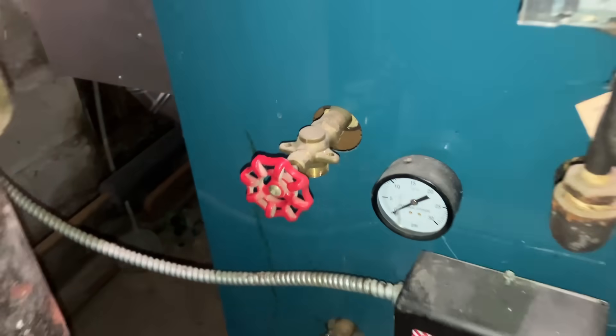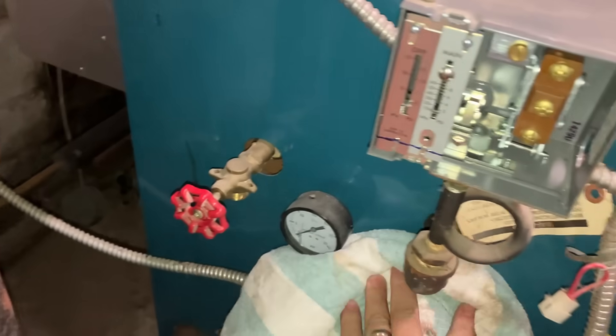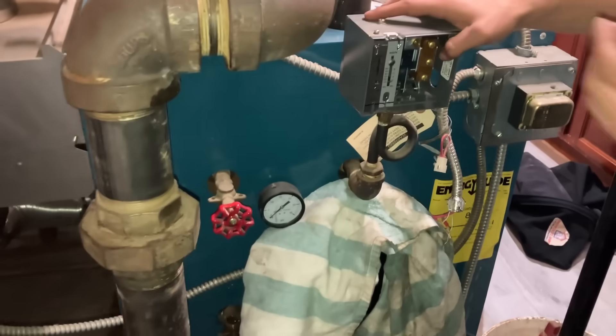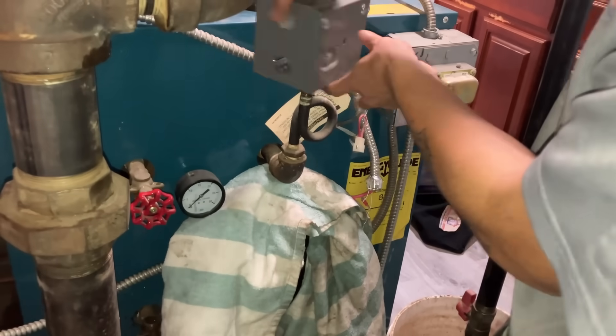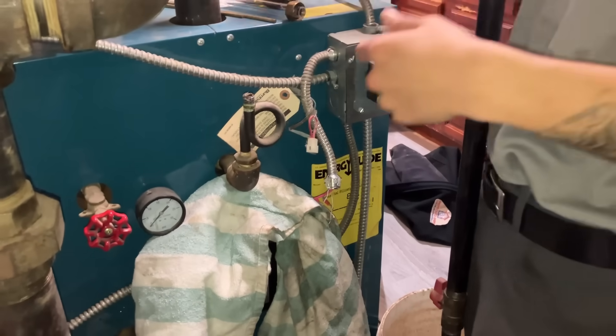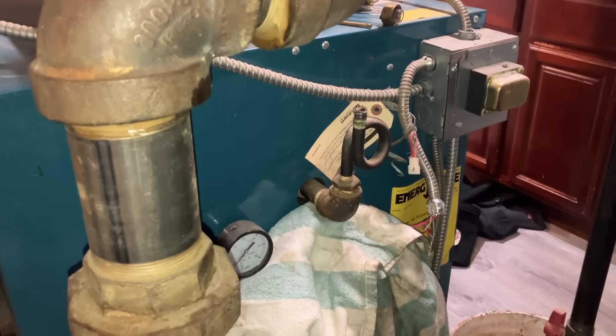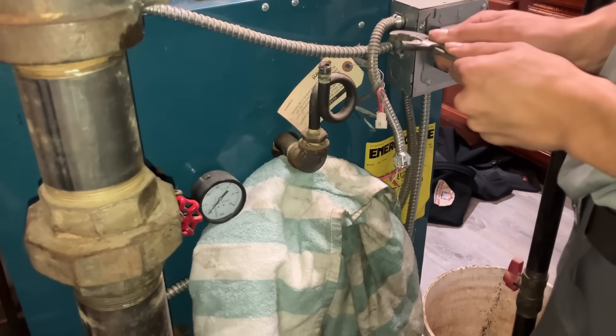They opened the top valve and nothing's coming out of it. Disconnected the Pressuretrol - let's put a rag right on top of the automatic feeder. Derek, spin off that Pressuretrol; there may be a little bit of pressure but not much. Let's take that pigtail out. All right, use a bigger channel lock - that little baby one is not gonna help you.